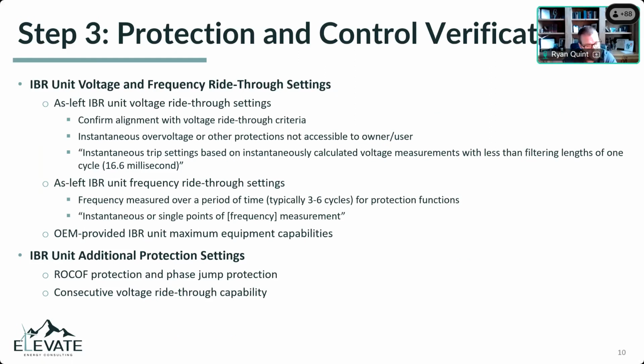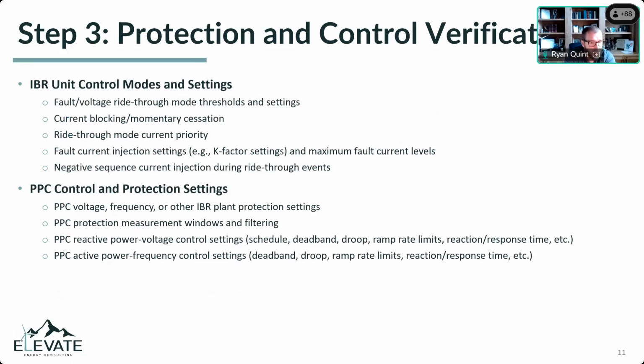And then there's the ROCOF and consecutive voltage ride-through capability that typically is a statement or some documentation coming from the OEM. Again, it's in some documents, it's not in other documents, it depends OEM by OEM. Then there are the control modes, the fault ride-through modes, current blocking / momentary cessation, reactive current versus active current priority, reactive power versus active power priority, and the continuous operation region, fault current injection, negative sequence current injection, PPC settings, gains, time constants, deadbands, reactive power voltage control, active power frequency control. Very rarely the PPC will have protections, but occasionally we've seen it, so we check that just to be safe. So again, we're just checking to make sure all of these things are set appropriately.